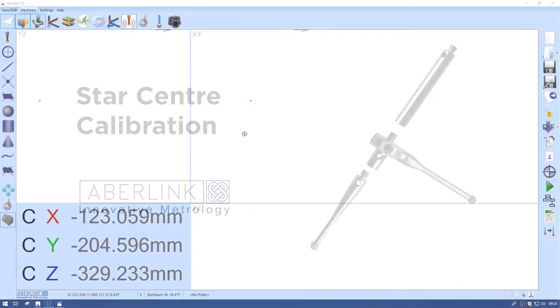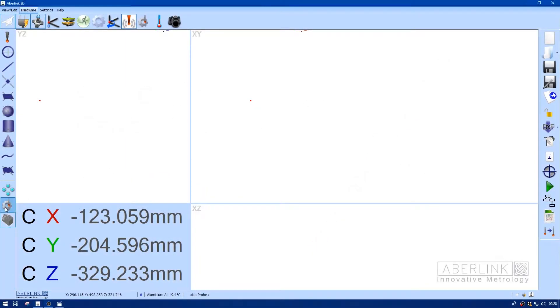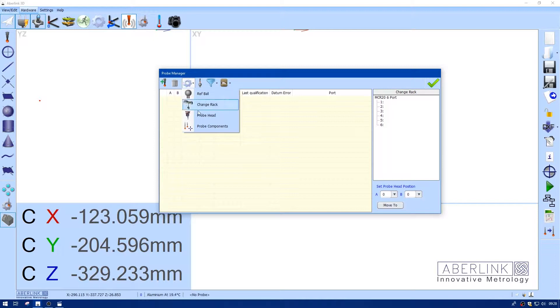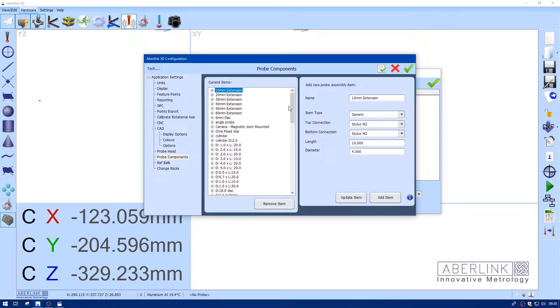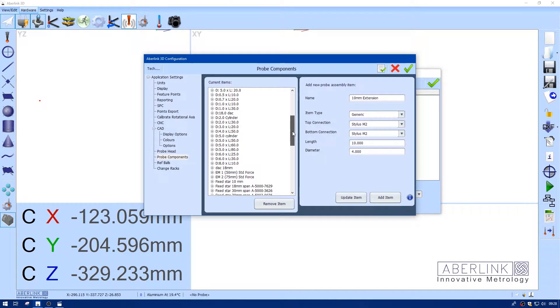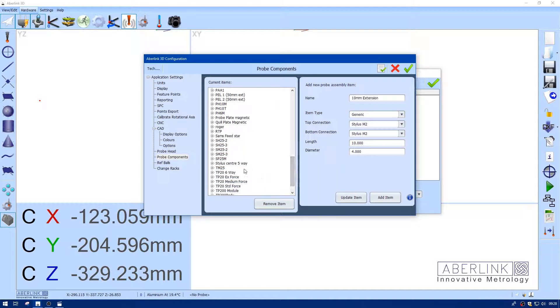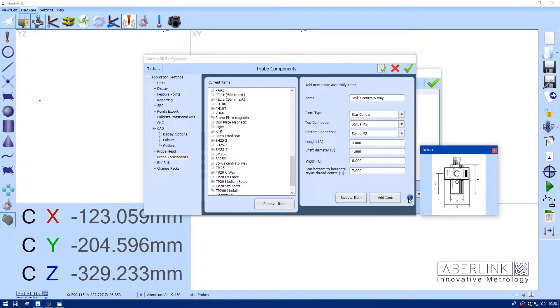First of all, we're going to go to the probe calibration page. We've just got to look at probe components, and we're going to find star center. This should be in your list already, but this just shows you how it's made. This information button here shows you the dimensions. These are already entered, so no need to worry.